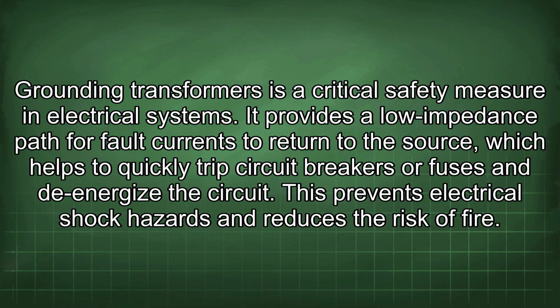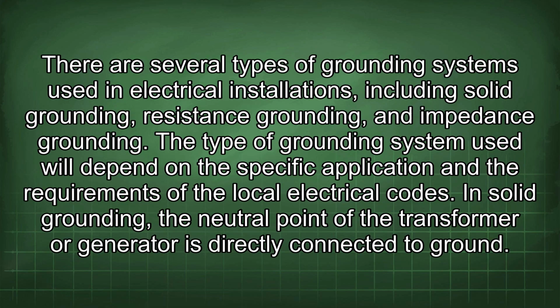Grounding transformers is a critical safety measure in electrical systems. It provides a low impedance path for fault currents to return to the source, which helps to quickly trip circuit breakers or fuses and de-energize the circuit. This prevents electrical shock hazards and reduces the risk of fire. There are several types of grounding systems used in electrical installations, including solid grounding, resistance grounding, and impedance grounding. The type of grounding system used will depend on the specific application and the requirements of the local electrical codes.